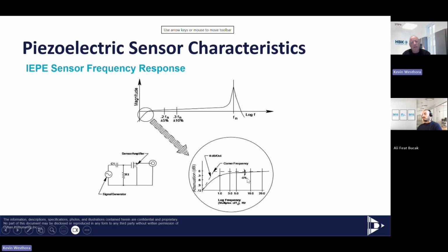So on the data sheet, we usually give you 2 points of data. We usually give you the 5% data point and then the 3 dB point, which looks like it's 1 hertz here on this accelerometer. Normally, the 5% data point is down here at, say, 1 hertz or 2 hertz. This is not typical of an accelerometer, this graph here, where they're showing it 5% at 7 hertz. That's not typical. Usually it's 1 hertz. All right, but it's important to understand this low end roll off of the accelerometer.